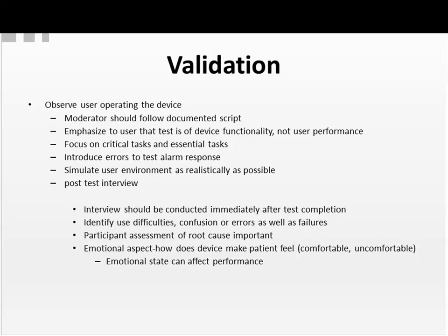This interview should be conducted right after the test is completed. You should address in this interview difficulties, any confusion, any errors that's noticed, as well as failures. You want to consider problems or potential problems as well as absolute failures. You should get the participants' assessment of any root cause of difficulties. Don't rely on the designer's reasons for a problem or a difficulty or a failure.